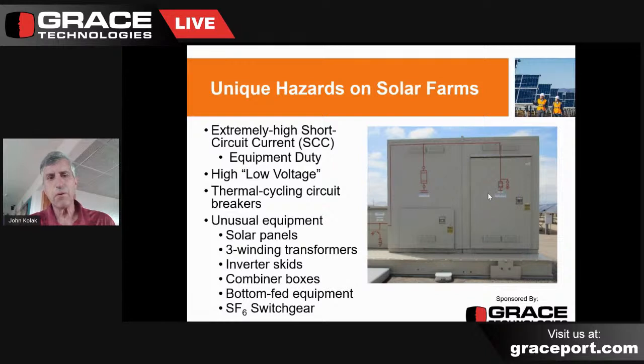So equipment duty is very important because if you have a circuit breaker, for example, that is not able to interrupt the fault current that's present on the farm, you'll have what's called a through fault. And that means that the current will go through that overcurrent device like a bullet, like it's not even there, and it will not be able to interrupt the current flow. What usually happens then is the next upstream device will clear the fault, or the worst of all scenarios would be that you actually burn in the clear. You melt the conductors or the bus bars, and it eventually clears itself. Of course, when you have those kinds of events happening, your finger's in the candle a long time, so to speak, and incident energy would be deadly. It would be unsafe at any speed.